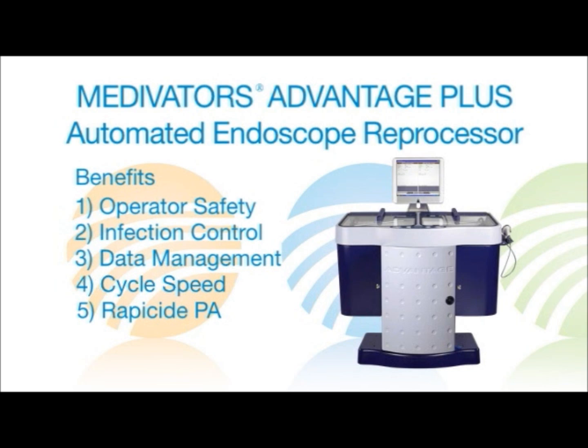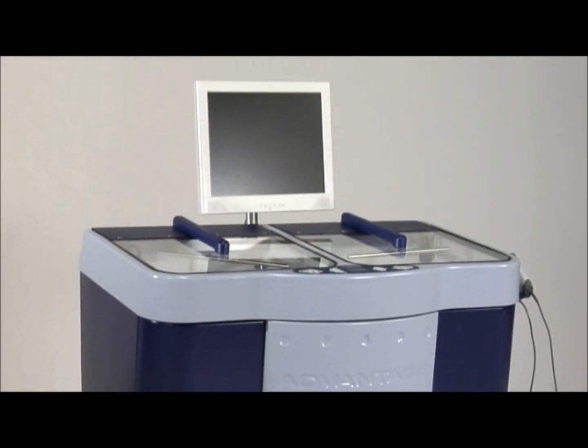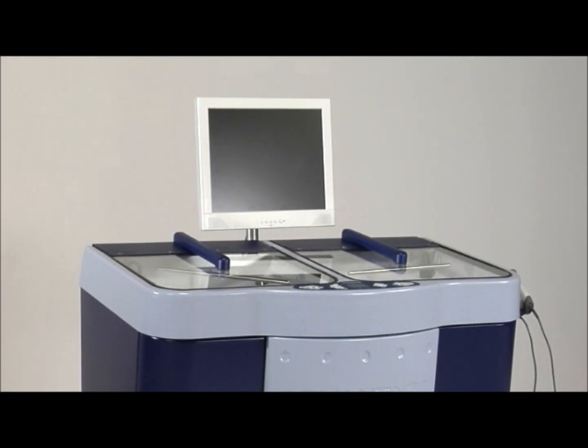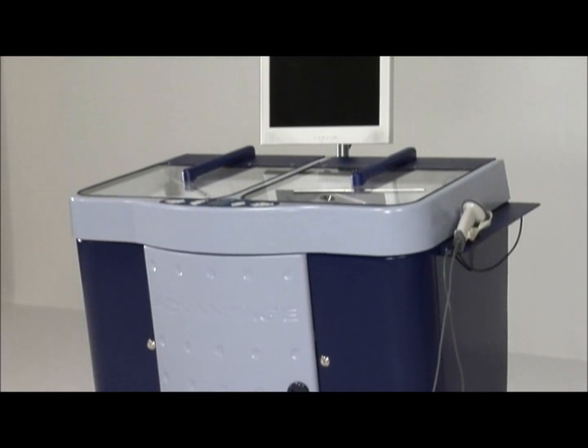These units provide a validated method for reprocessing endoscopes in as fast as 22 minutes after manual cleaning. Medivators is committed to the highest quality of patient care. After the endoscope is cleaned in accordance with the instructions provided in the scope instruction manual, this reprocessor will help to ensure operator and patient safety.